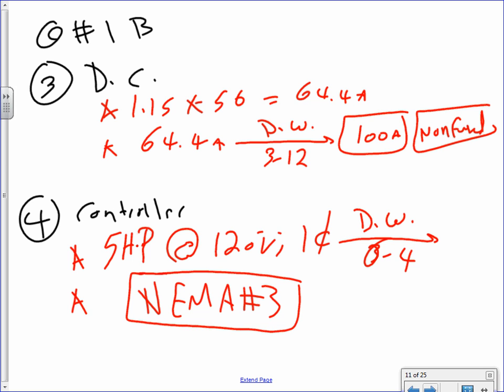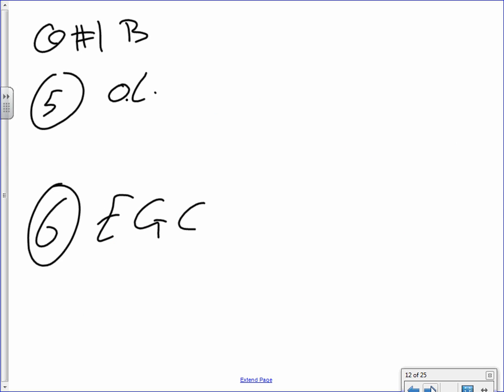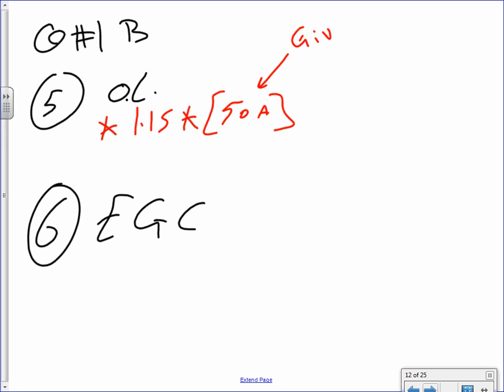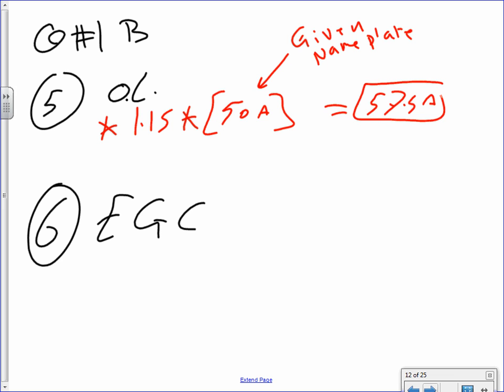Okay. So let's go to the next one, which is the overload. I have no idea what the overload size is, so I'm going to take 1.15 multiplied by the nameplate, 50 amps. Where did this 50 amps come to be? I'm going to say nameplate given. So that will get you 57.5 amp. 57.5 amp. Done.